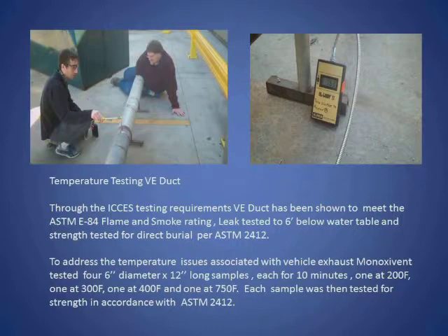Now the ICC requirements, they tested it for flame and smoke. They leak tested it to 6 foot below the water table, and they strength tested it using ASTM 2412. And then, as I mentioned, the way we addressed the temperature was to set up this procedure and run these 4 samples at 200 degrees F, one at 300 and one at 400, and then we took the last one up as high as we could get it, and we had about an average of 750 for 10 minutes. Each sample was then strength tested in accordance with 2412.